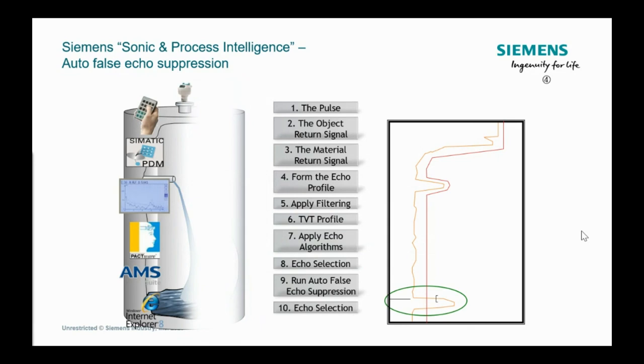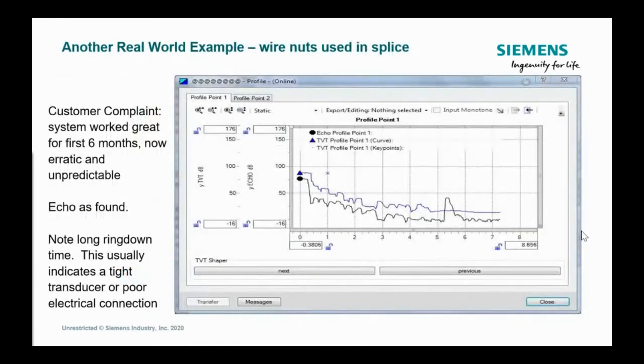Had a customer, they were having some trouble where their complaint was that the system worked great at first install, worked for about 6 months, really great, and now they were getting erratic and unpredictable measurements. Sometimes working with the echo profiles is kind of like reading the tea leaves. You have to see a few of them and get an understanding. One of the things I do suggest to folks all the time, if you're calling tech support, is to get a picture. Cell phones are a wonderful thing. Get a picture of that echo profile off of the display screen, or if you have PDM, capture it as a JPEG image, use a snipping tool or something like that. If you send that in to tech support and they can see what the process is doing, usually that's going to give you a quick indication.